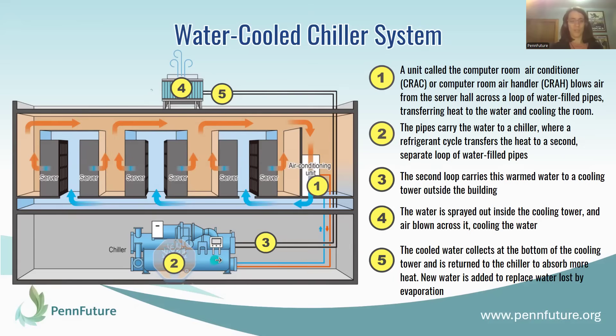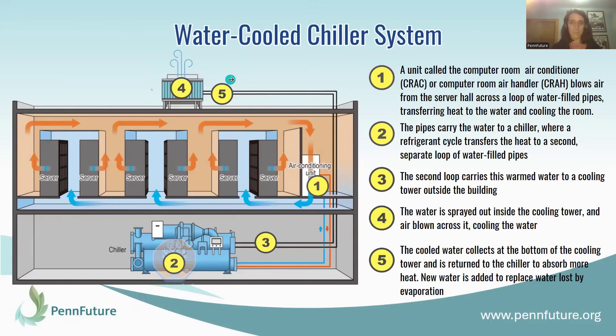The water then circulates down into the chiller, and inside the chiller there is a refrigerant cycle that takes the heat from this loop of water and transfers it to a separate loop of water — so these two water loops do not mix. Once the heat is transferred to this second loop of water, it gets pumped outside the building into a cooling tower. The loop of water from the server room has now cooled down due to this cycle, so the cool water is pumped back into the air conditioning unit, and the cooled air is blown into the server room where it cools down the servers.